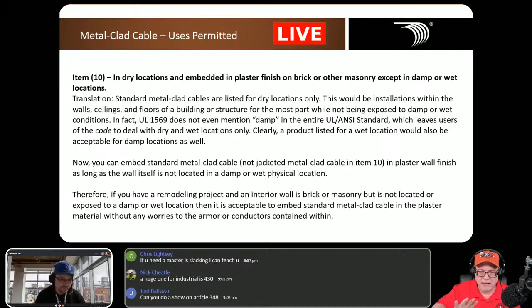Okay? So if it's a dry location and it's plaster finish on brick or masonry, then you can embed it into plaster all you want. Plaster will dry out. It's not an issue. But as long as it can't be in a damp or wet location. Now, interesting enough, in the NEC, when it comes to 330 for MC cable, we either have dry or we have wet. We have nothing in there about damp. In fact, this is the first time you see damp at all in 330, okay? And the reality is 1569, the standard for MC, doesn't even mention the word damp. So if it's wet, then it is more restrictive than damp. So anything that's wet is okay for a damp location. Anything that is dry generally applies to a dry location. So if I've got a damp location, then I'm going to go with the wet rated MC. Okay, because that's more restrictive. Okay.